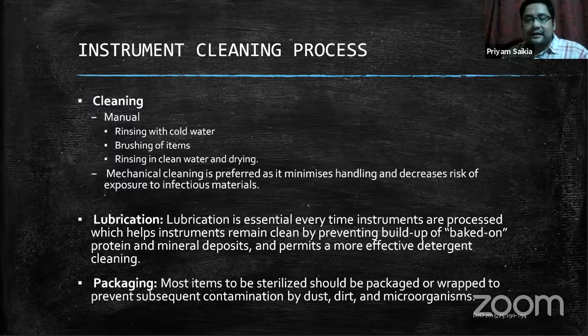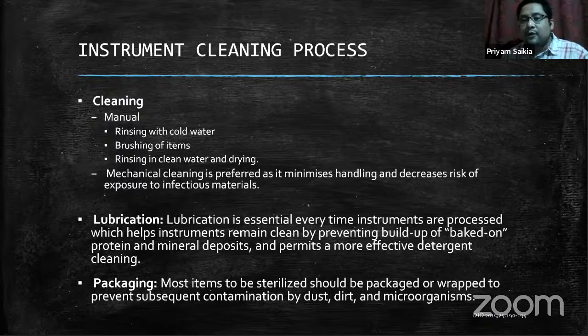While we do manual cleaning, the rinsing of the equipment should be under cold water and it should be under running water, and the equipment should be opened up if that can be opened, because if we do not open the instrument, then some of the organic matter will not be washed away. Then it should be done under cold water, that is in and around 25 degrees Celsius. Otherwise, this might cause denaturation of the proteins which are on those instruments, and that can cause problems with disinfection. And this should be done under running water. Otherwise, brushing of those equipments will lead to generation of aerosol that will cause cross-contamination. That is the reason the brushing should be done under running water.